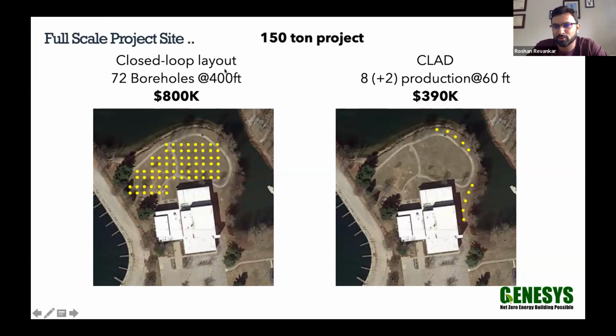So compare that to 400 feet deep and drilling 72 boreholes on site and tearing up the whole lot or the whole play area. In this case, we are going around here. For this particular project, we had 2 options of discharge. One is we could discharge into this lake, and another option was to discharge into discharge wells. Obviously, it was cheaper to discharge into the lake, so that's what we are doing.